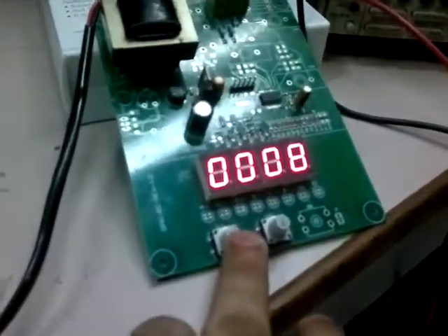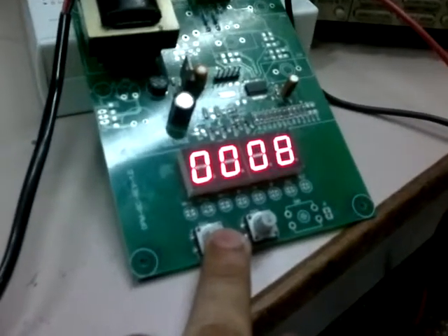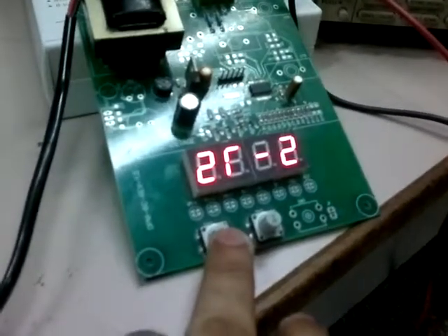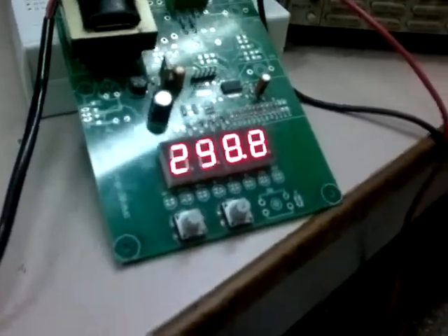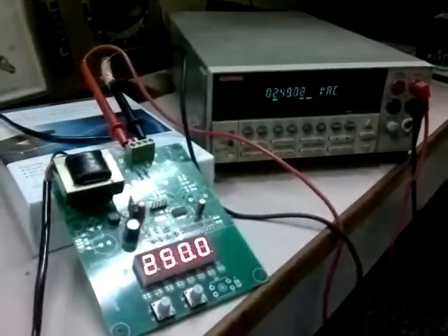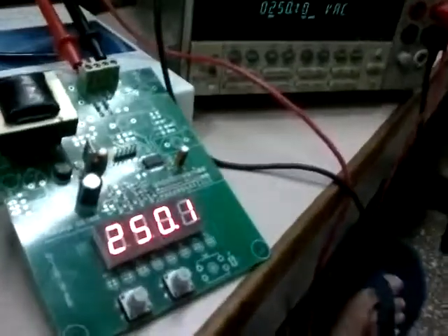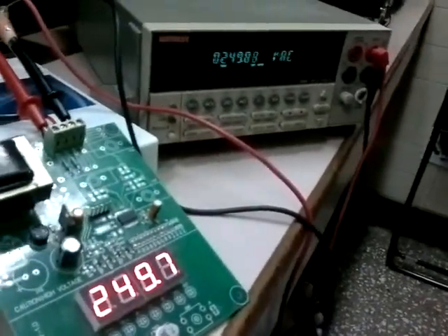This is just showing you the zero counts. There's nothing we have to do here. This is only for our observation. Now we will try to compare the calibrated DPM with the meter. So now we can see that both are showing approximately 250 volts.